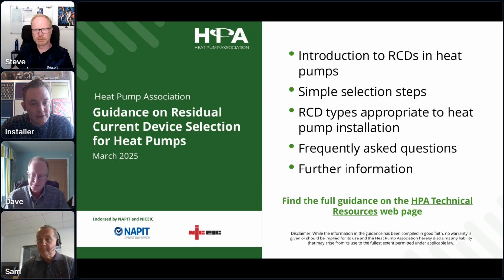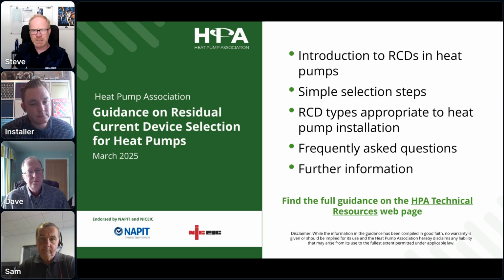Who fancies explaining tripping to us? I think I can talk about some of the dangers around DC blinding of RCDs, which is something that is not new. It's been around for a while, and it's really important, like Dave just mentioned, that this selection is so important because things like this can happen. So in simple terms, RCD blinding is an incident that occurs when the RCD is saturated by DC current or sometimes exposed to high frequency waveforms. And this is going to prevent it, like Dave just said, from operating under fault conditions, or can reduce its sensitivity. So the RCD is not acting like it should do.